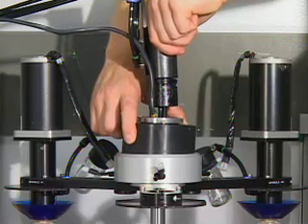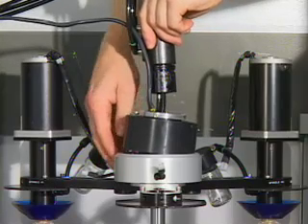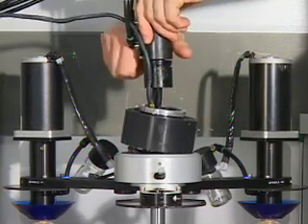Pull rotary union out of brush block and remove from assembly. If you are replacing rotary union only, leave brush block cords in the hub assembly.